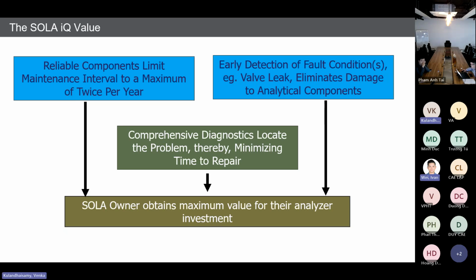But in SOLA 2, if you want to replace the glass tube, you have to open up and remove the heater from the heater assembly separately, then the U-tube assembly separately, and only then can you replace the glass tube. But here, no need to remove the entire assembly. Just open the two end caps, which are quarter-inch ferrules, and you can easily replace the ceramic tube within 5 minutes without opening the total pyrolyzer.